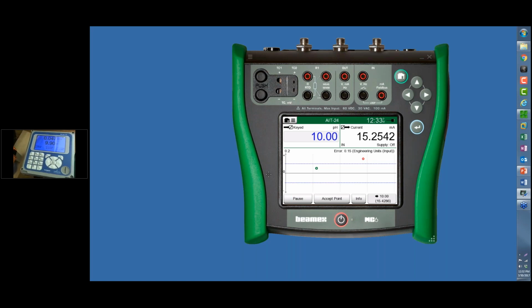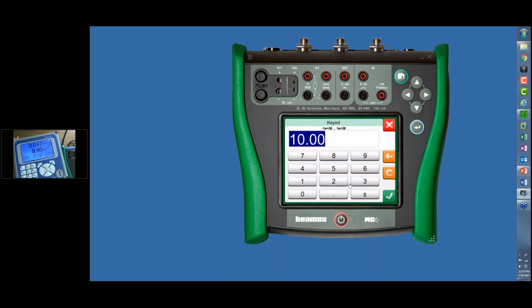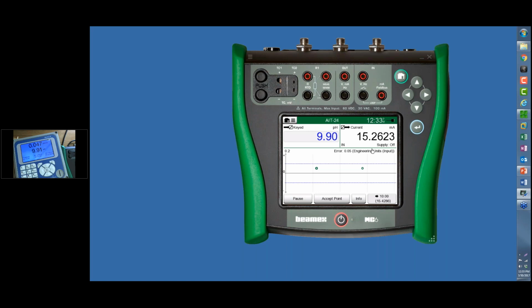The tolerance that I picked out for this test is 0.1 pH. And right now we're sitting at 9.9. And again, there's my station. Let me hang this up here again. So we're at 9.9. If I go into the calibrator and pick 9.9, that is what we're seeing. Given this current that we're actually measuring, we are getting about 0.05, 0.04 pH error.